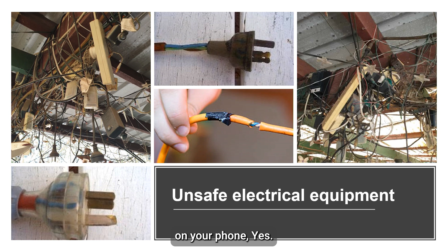Next, RCDs, residual current devices. Everyone in this room by now should know what an RCD is. If not, where have you been for the last 15 years? In your electrical switchboard, you should have both circuit breakers and RCDs. A circuit breaker or a fuse protects the cable whereas RCDs are designed to protect you. RCDs will, when properly installed and maintained, provide high levels of personal protection from electric shock. You must ensure that any electrical risk associated with the supply of electricity to plug-in electrical equipment, such as anything that plugs into a socket outlet, is minimized by the use of an appropriate RCD.